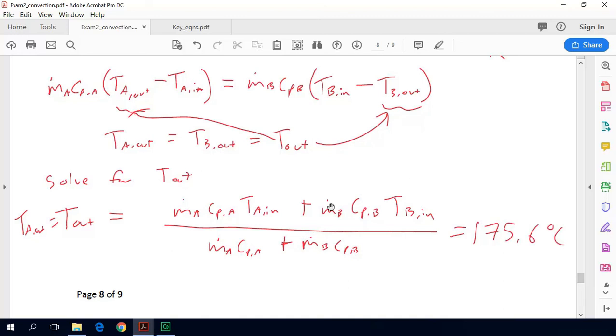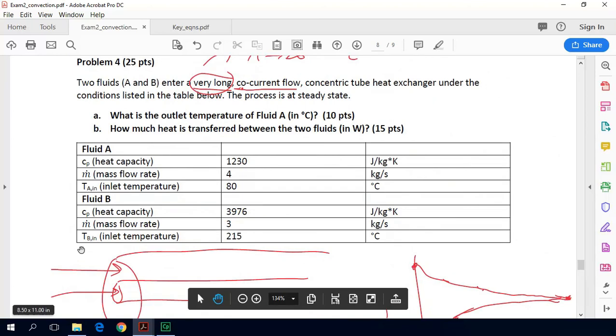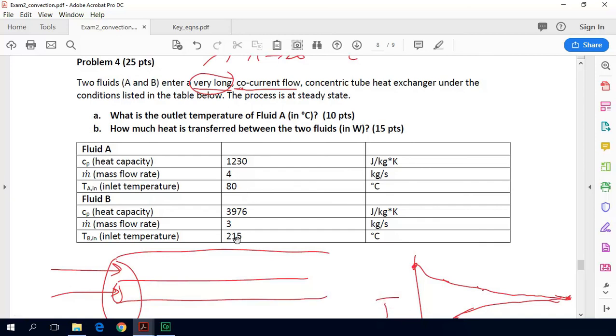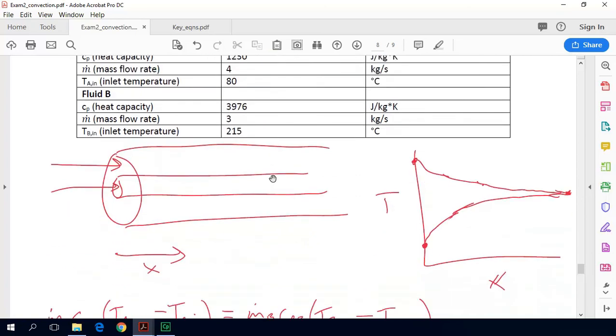And again, as always, I usually skip the plugging and chugging, but that part is important to make sure we have all the units right and that we get a number that makes sense. So does this 175.6 make sense? So fluid B comes in at 215, fluid A comes in at 80, and they meet somewhere in the middle. That somewhere in the middle is a little bit closer to the fluid B temperature because it has the higher heat capacity rate, which is M dot B times CP B. That number ends up being substantially higher than fluid A. So the way this graph would really look would be something more like this. Or that final temperature is closer to the fluid B temperature because it has the greater capacity to give off heat.